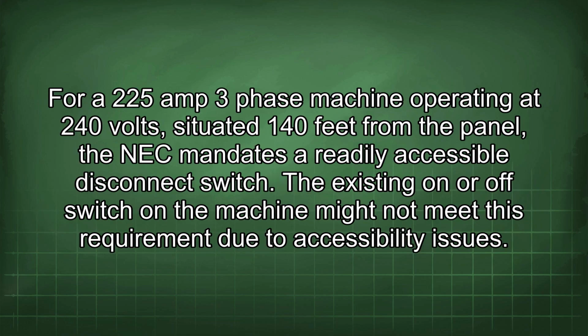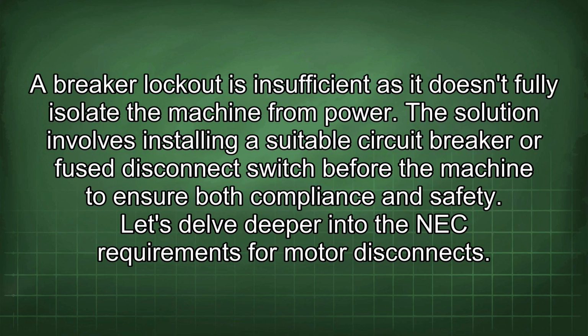For a 225 amp 3-phase machine operating at 240 volts, situated 140 feet from the panel, the NEC mandates a readily accessible disconnect switch. The existing on or off switch on the machine might not meet this requirement due to accessibility issues. A breaker lockout isn't sufficient as it doesn't fully isolate the machine from power. The solution involves installing a suitable circuit breaker or fuse disconnect switch before the machine to ensure both compliance and safety. Let's delve deeper into the NEC requirements for motor disconnects.